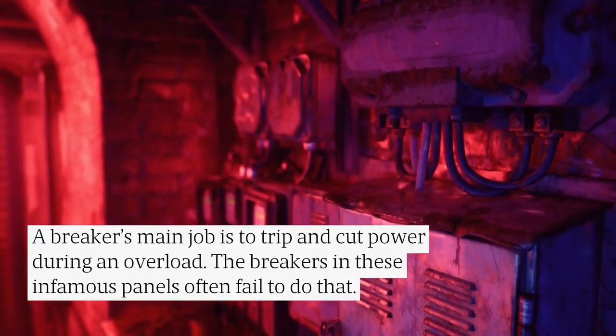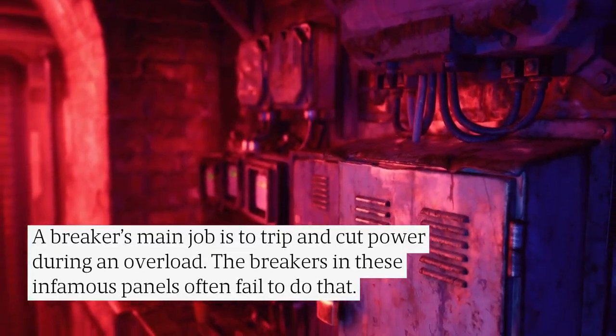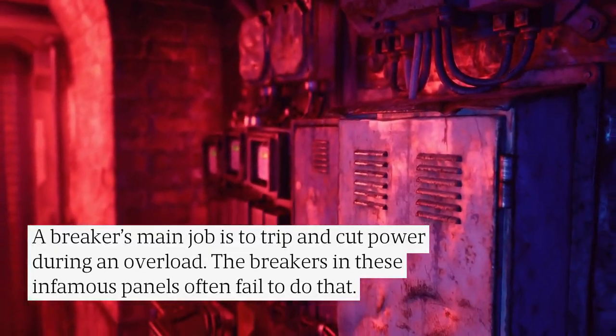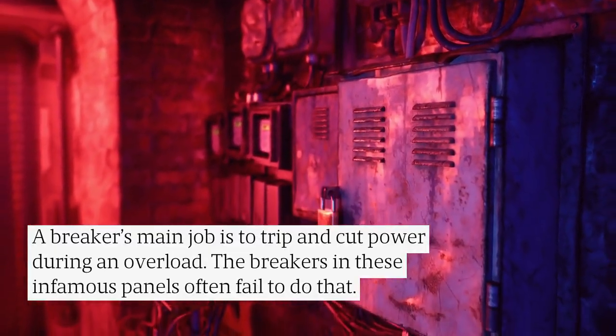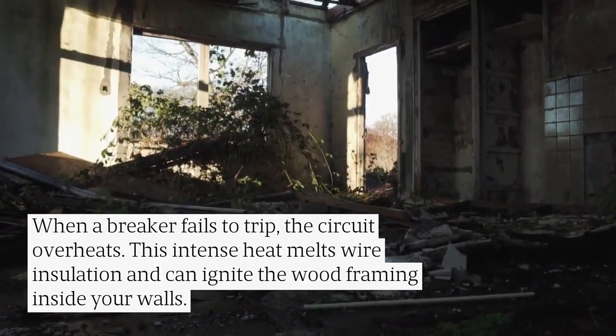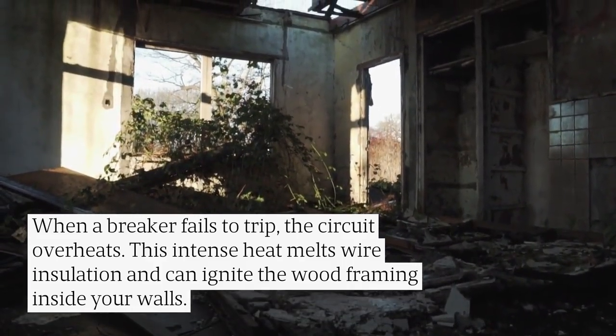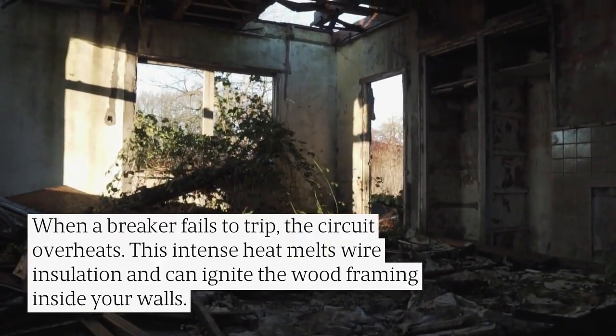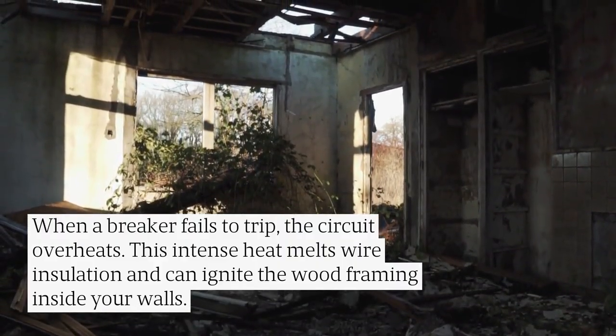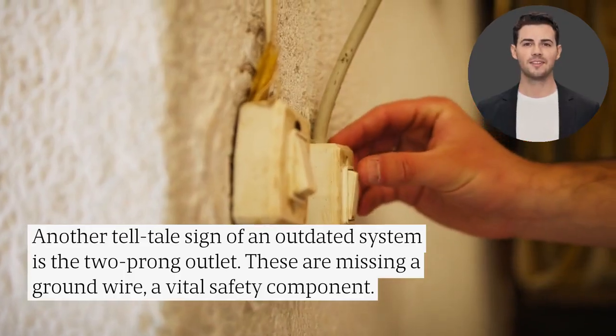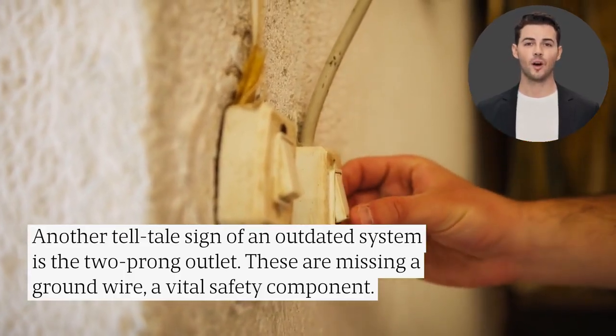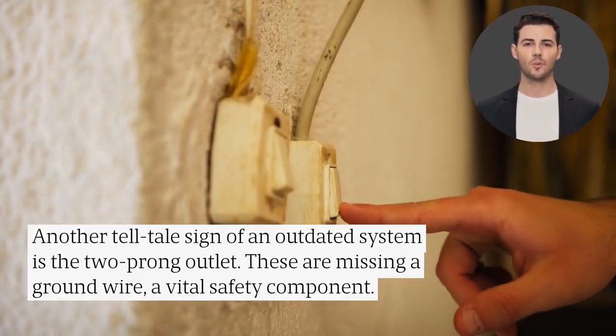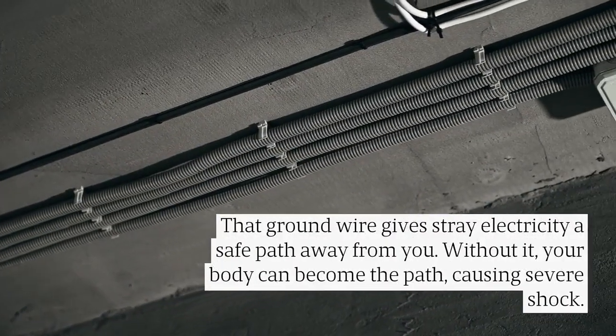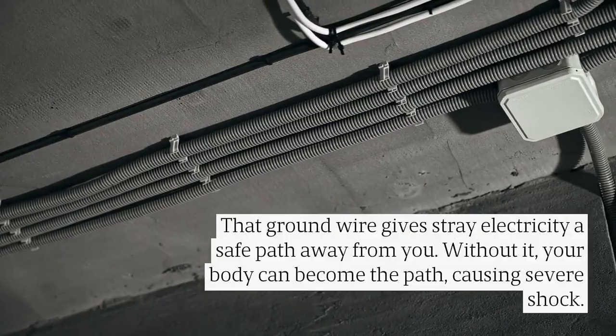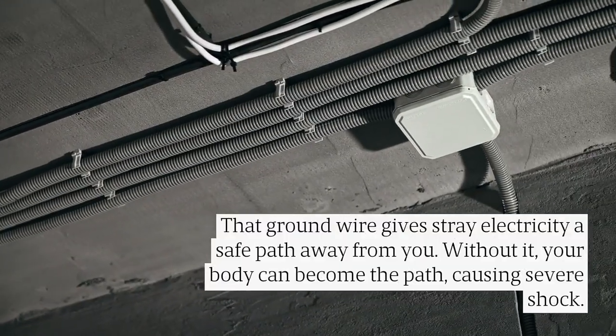A breaker's main job is to trip and cut power during an overload. The breakers in these infamous panels often fail to do that. When a breaker fails to trip, the circuit overheats. This intense heat melts wire insulation and can ignite the wood framing inside your walls. Another telltale sign of an outdated system is the two-prong outlet. These are missing a ground wire, a vital safety component. That ground wire gives stray electricity a safe path away from you. Without it, your body can become the path, causing severe shock.